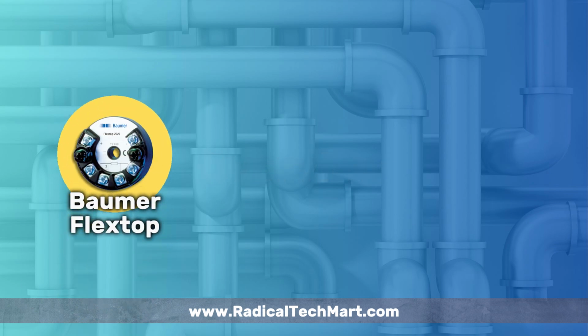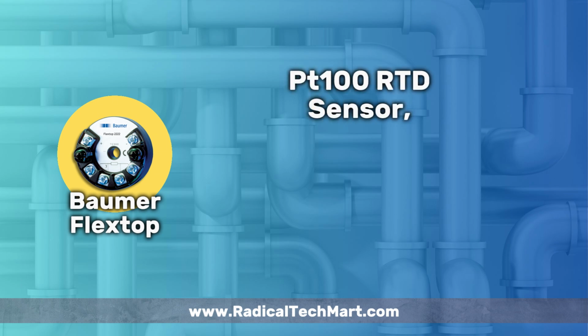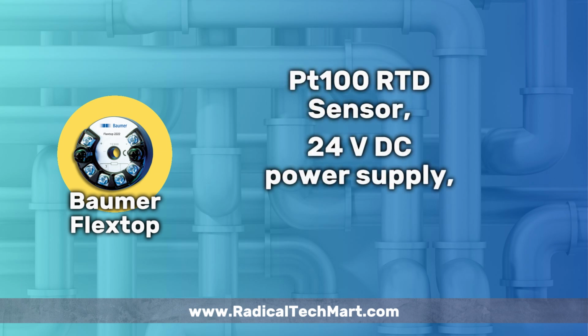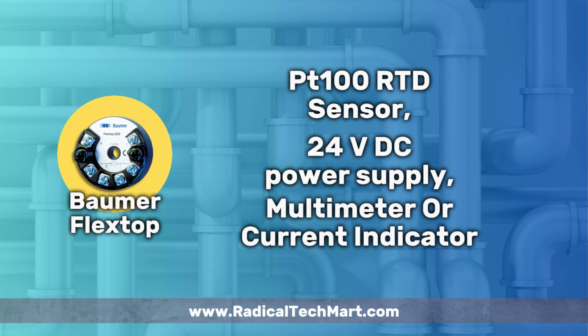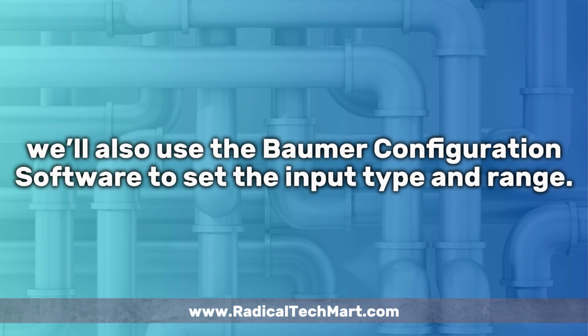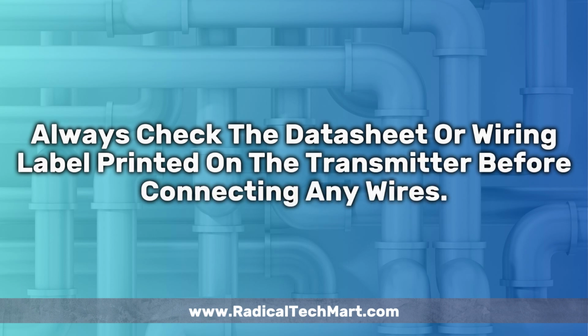Here's our Baumer Flextop 2222 transmitter, a PT100 RTD sensor, a 24-volt DC power supply, and a multimeter or current indicator to measure the loop output. We'll also use the Baumer configuration software to set the input type and range. Always check the datasheet or wiring label printed on the transmitter before connecting any wires.